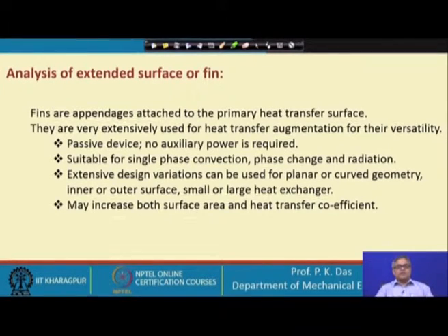The heat transfer may also increase by the fin design. Definitely we are increasing the surface area, but by our innovative design we can sometimes increase the heat transfer coefficient also. Sometimes, by a good design in condensation, we can promote the drainage of the condensate film, which is very important. Then as it is a passive device, it will have the features of a passive device. That means it is highly reliable, low maintenance, all these things are there.